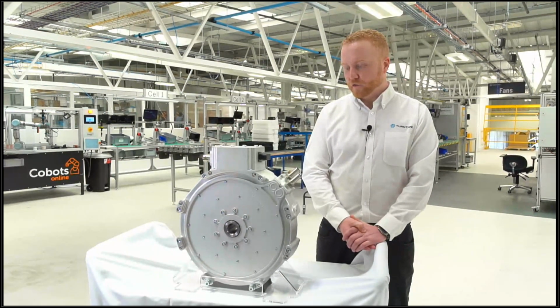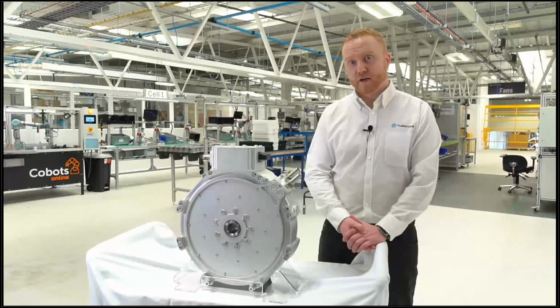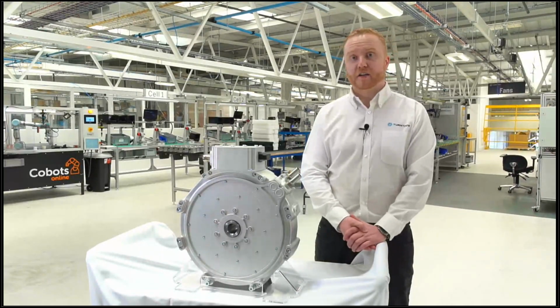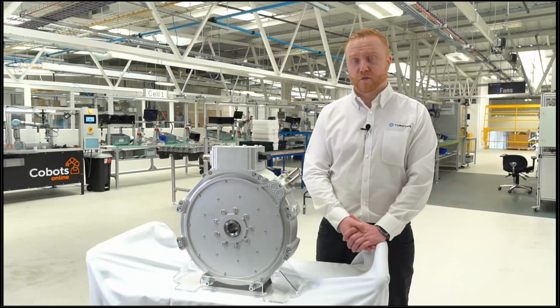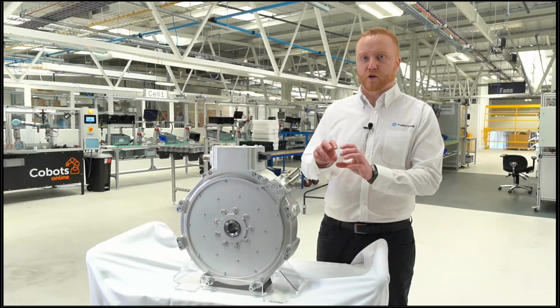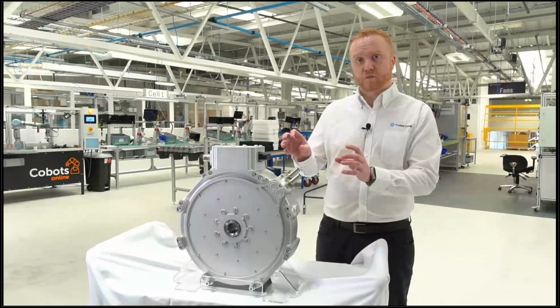We've integrated PT100 temperature sensors within the windings of the stators, directly embedded within the end windings, which are the copper windings that protrude from the stator core.